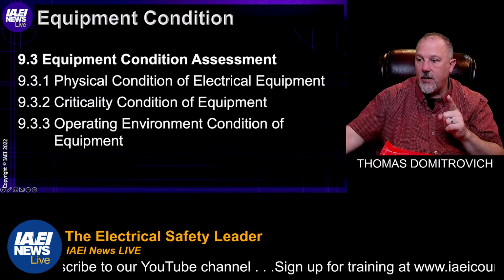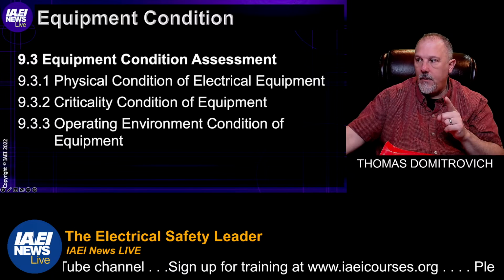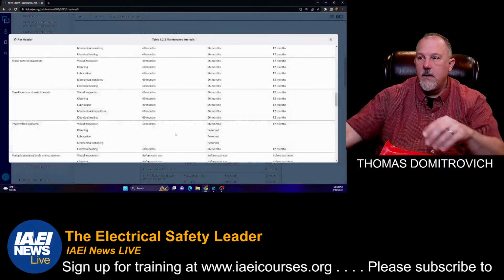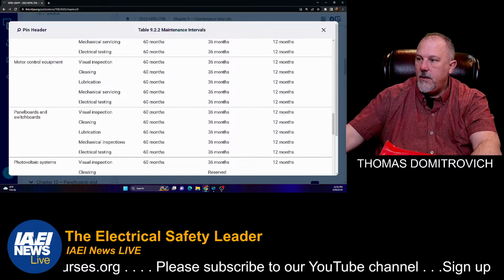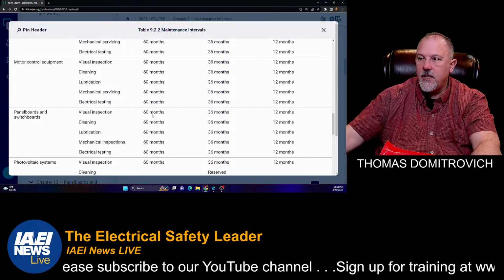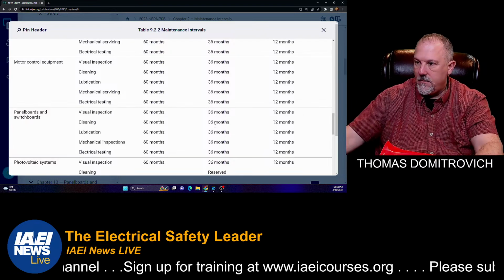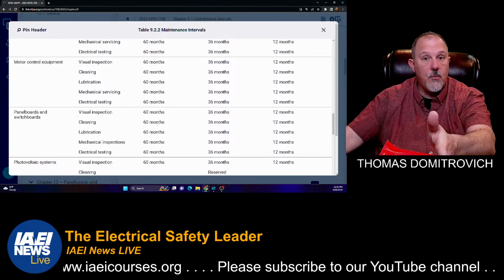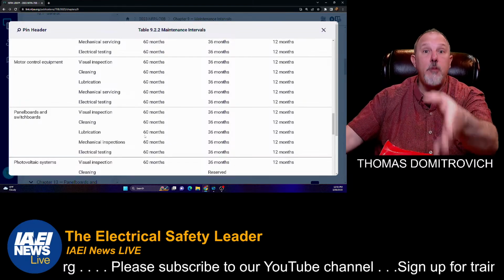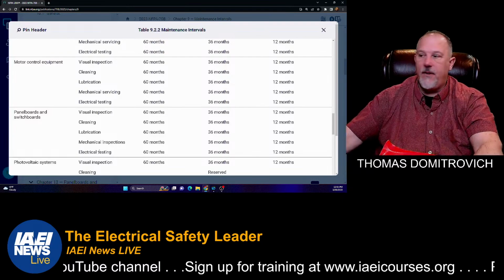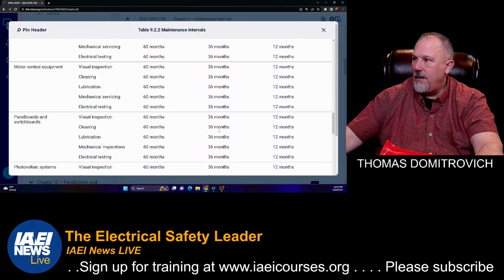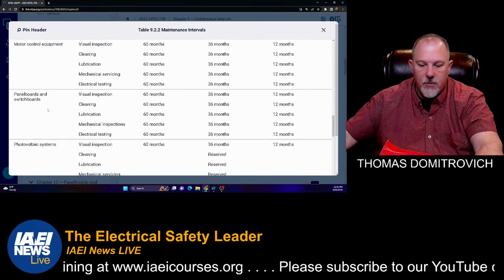So for panel boards in general, there we go. There's your panel boards. It says visual inspection every 5 years, 3 years, and annual. This is condition 1, 2, and 3. 1 is the best, 2 is middle of the road, 3 is worst case. You're going to do a visual inspection every 5 years. You're going to clean it every 5 years. I'm going to assume condition 1. You're going to lubricate anything that needs to be lubricated every 5 years. You're going to do a mechanical inspection every 5 years. You're going to do electrical testing every 5 years. So it's 60, 36, 12. 60, 36, 12 for panel boards and switchboards.